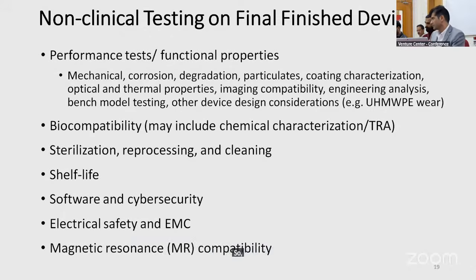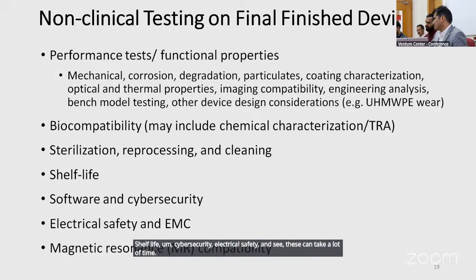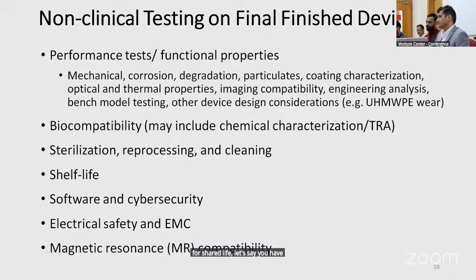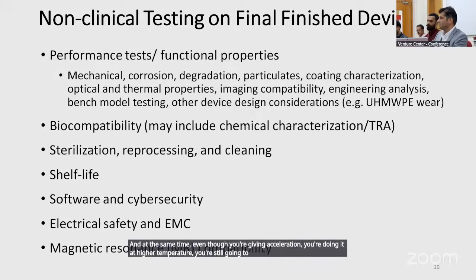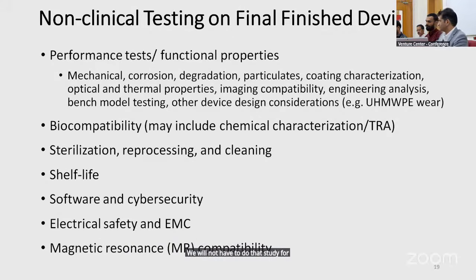So you want to be careful of, or just be aware of, what testing exists and what the requirements for that are. Shelf life, cybersecurity, electrical safety, EMC, these can take a lot of time. So shelf life, let's say you have a 5-year shelf life, that's going to take like 3-4 months, even when you're doing accelerated aging. So it's going to take time. You're going to have to wait it out. And at the same time, even though you're doing accelerated aging, at higher temperature, you're still going to need real-time aging as validation. So you're going to have to do that study for 5 years and then keep that data in your TMF if it's needed. So again, you have to plan ahead for this.